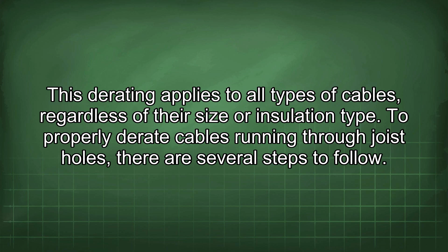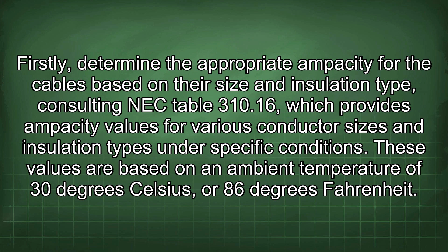Firstly, determine the appropriate ampacity for the cables based on their size and insulation type, consulting NEC Table 310.16, which provides ampacity values for various conductor sizes and insulation types under specific conditions. These values are based on an ambient temperature of 30 degrees Celsius or 86 degrees Fahrenheit. If the ambient temperature is higher, additional derating may be required.